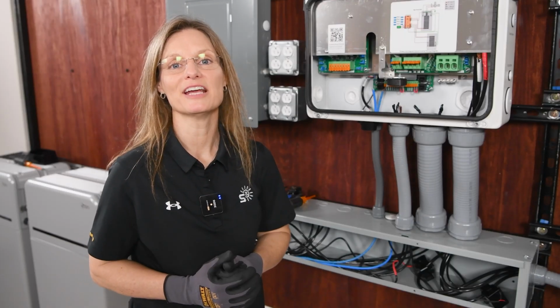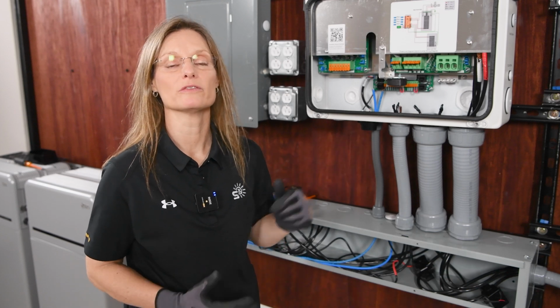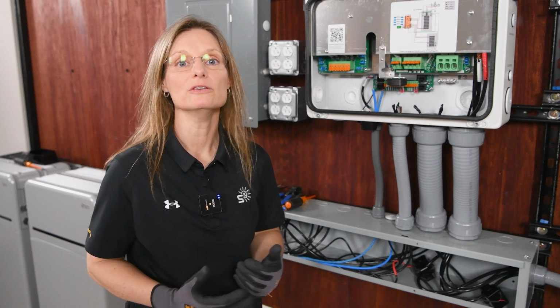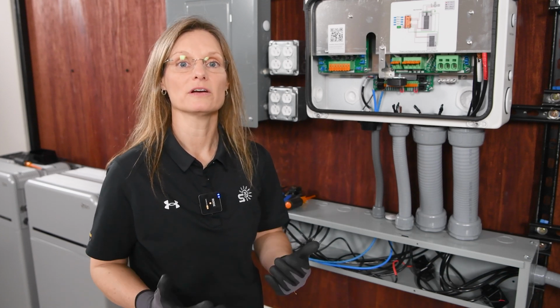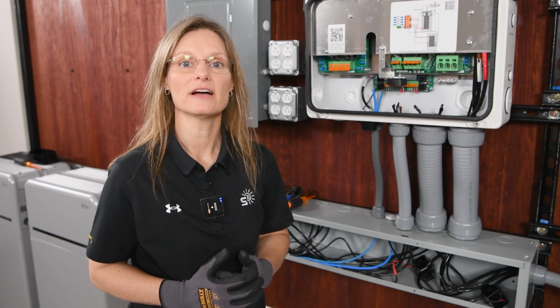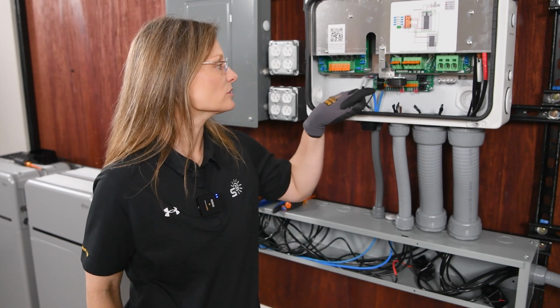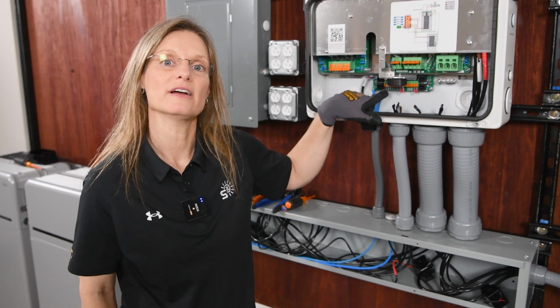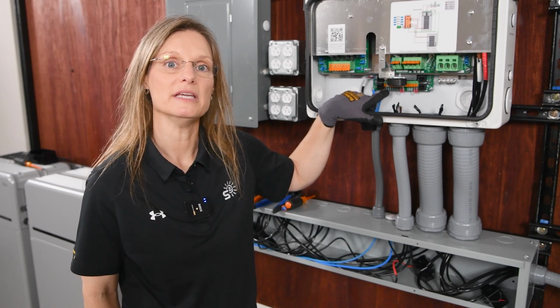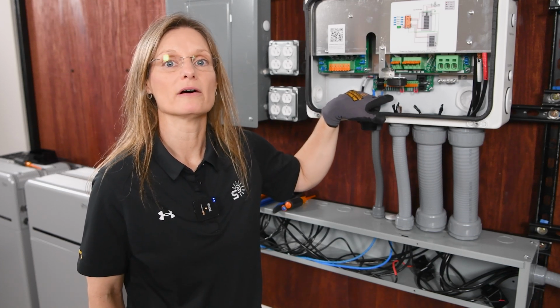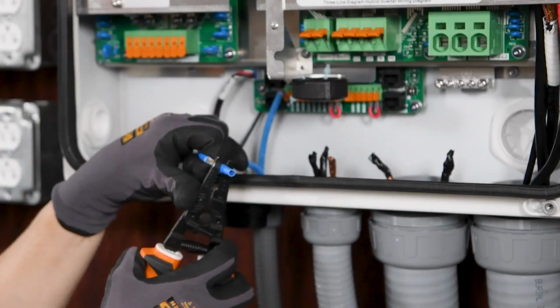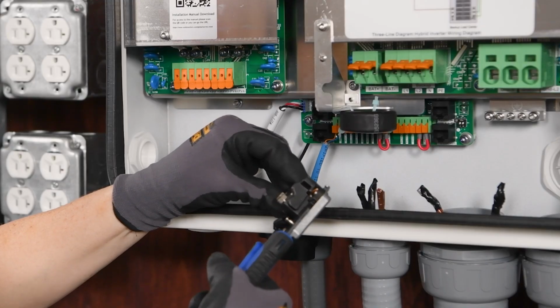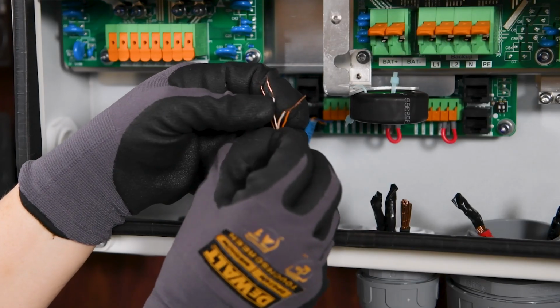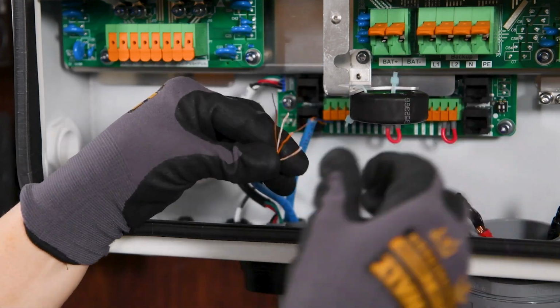Next, we'll set up our communications with our LG batteries and our board for our inverter. We will not use the CAN communications. With LG batteries, it's RS485 communications. So we'll start on our board here with RS485A, RS485B, enable and enable ground. Whichever colors we decide to use on our RS485 cable, we'll just need to make sure and match those up with the connections in our LG batteries.